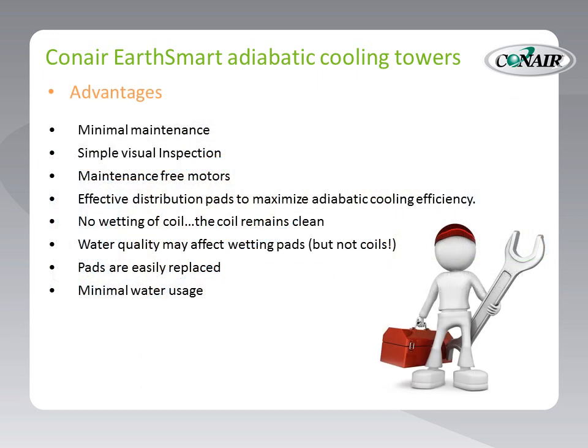Maintenance is simple on the EarthSmart tower and in most areas requires just a visual inspection. The fan motors do not require a lubrication regimen, and wetting pads may require cleaning or replacement depending upon local water quality. Coils may require cleaning if pads are removed for winter operation.